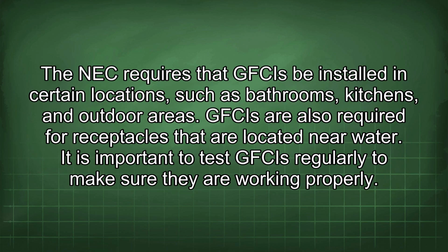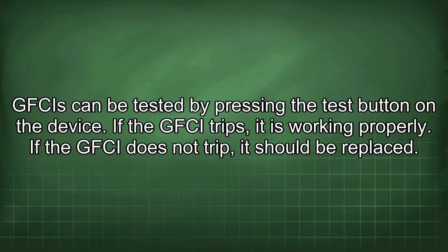The NEC requires that GFCIs be installed in certain locations such as bathrooms, kitchens, and outdoor areas. GFCIs are also required for receptacles that are located near water. It is important to test GFCIs regularly to make sure they are working properly. GFCIs can be tested by pressing the test button on the device.